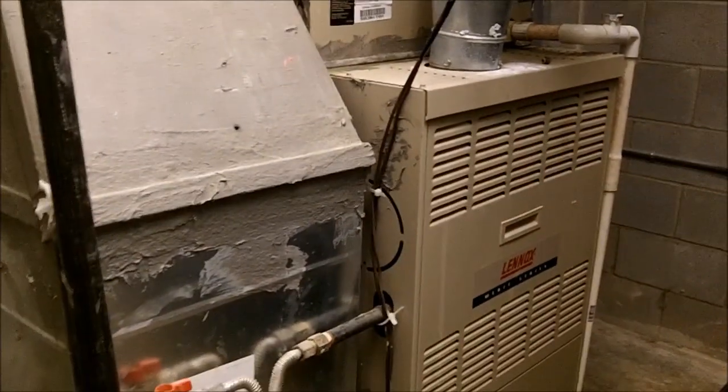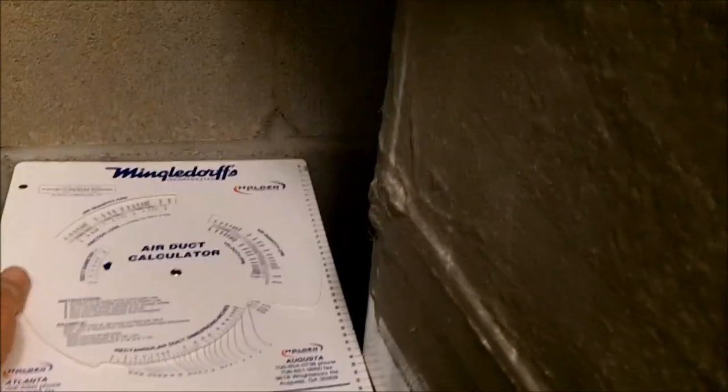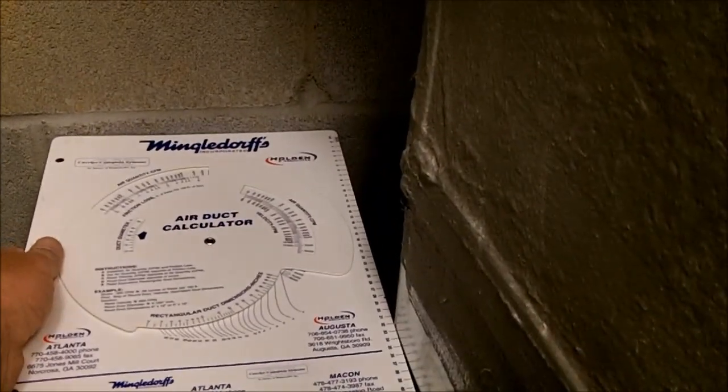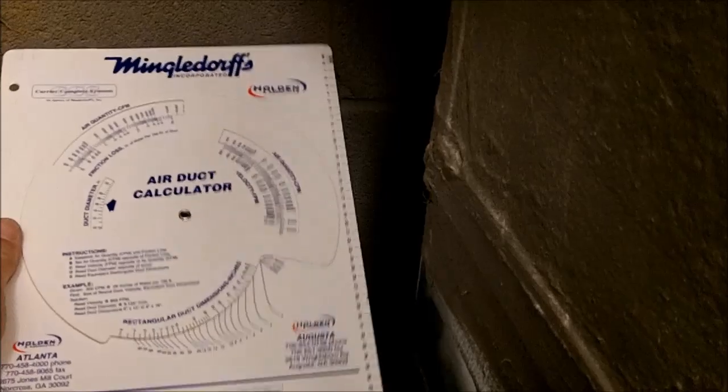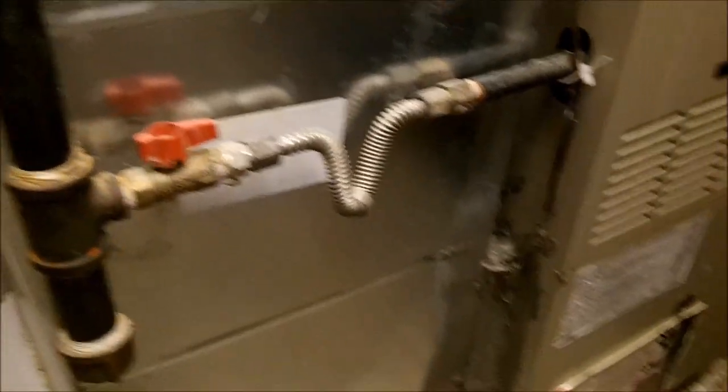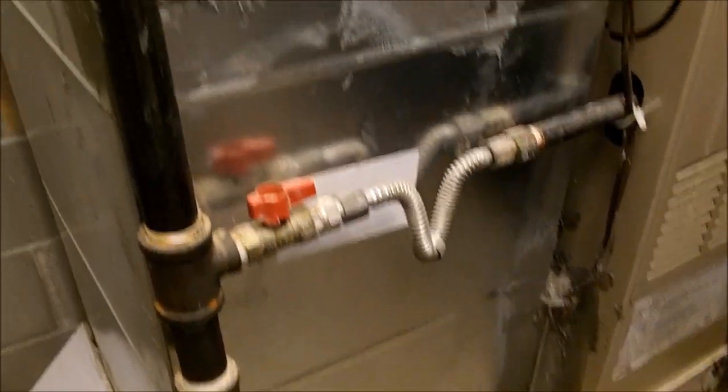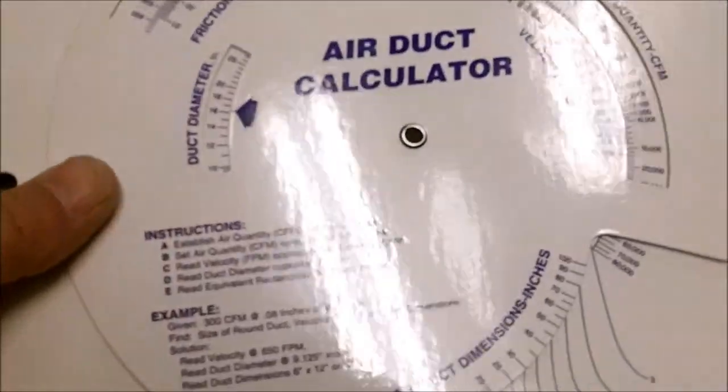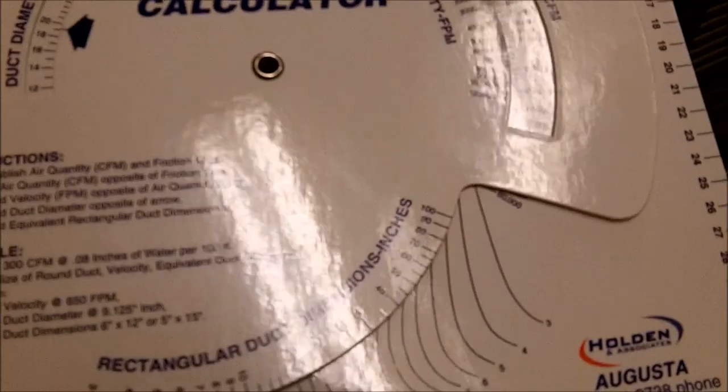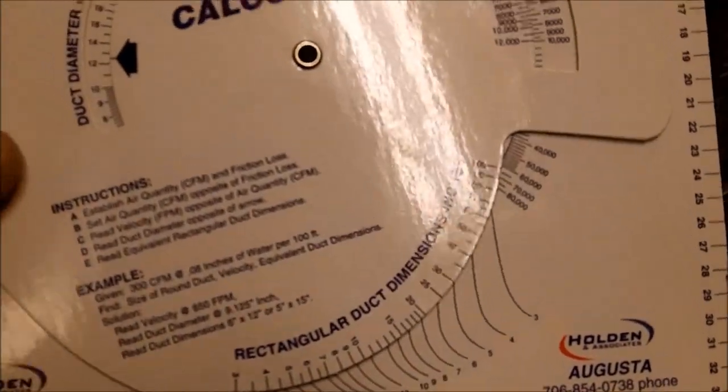When you look at it from the front, it's really tough to get in here because I just don't have enough room. You think, oh, no big deal. But when you go to the back, you see how much room is there. What they've done is they've put 18 by 16 lined duct, which makes it 16 by 14 for a five-ton system. We'll look at the duct size in a little bit according to the duct calculator.